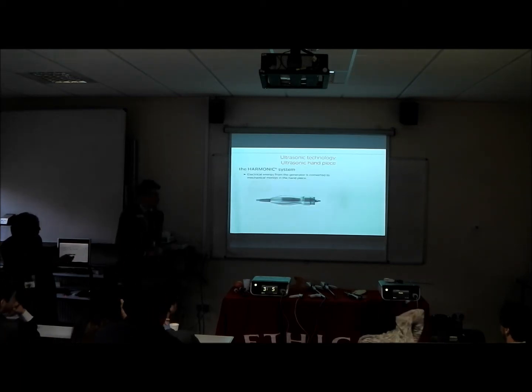Basically, what happens is, I'm just going to briefly tell you. You know the audible range of sound, so we are using it at more than 20,000 hertz. This is the harmonic scalpel I'm showing you here. This is what I'm using most of the time, because there's no electric current, no electricity flowing in and out of the patient, and no worry about the equipment working or not working. So this sound energy is what we're using. If we move on, we've got a handpiece.